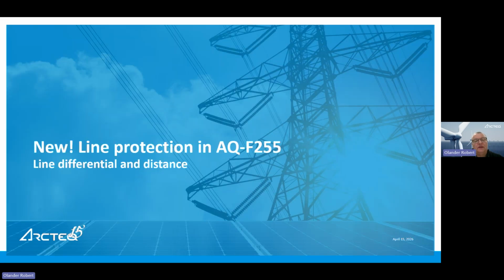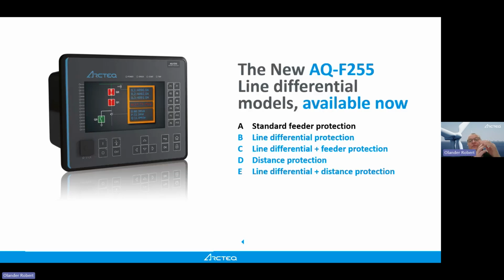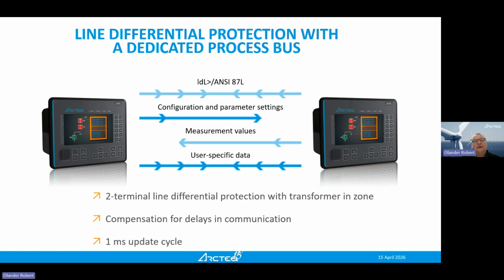Okay, this was it. And now let's go into some news. The line protection. So basically, this line protection is in the feeder protection F255. So it's actually added options to these, and you can see from here that if you take AQF255A, it's a standard feeder protection. If you take B, C, D, E, then it's different level of line protection included in that. So the B and C is line differential, D and E is distance protection, or then combined line differential and distance protection. And the line differential is like a peer-to-peer.